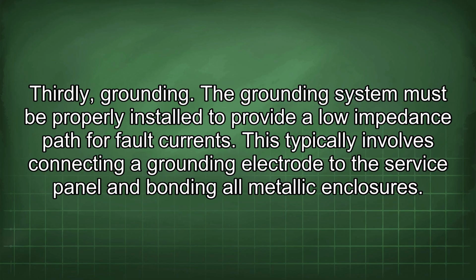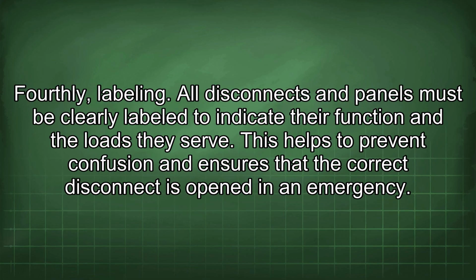Thirdly, grounding. The grounding system must be properly installed to provide a low impedance path for fault currents. This typically involves connecting a grounding electrode to the service panel and bonding all metallic enclosures. Fourthly, labeling. All disconnects and panels must be clearly labeled to indicate their function and the loads they serve. This helps to prevent confusion and ensures that the correct disconnect is opened in an emergency.